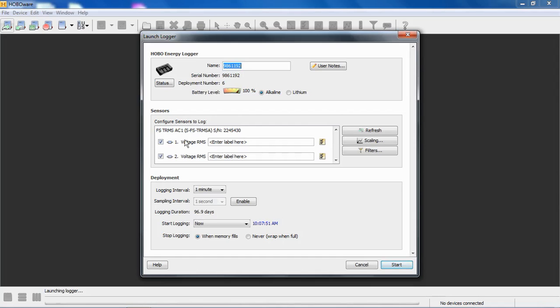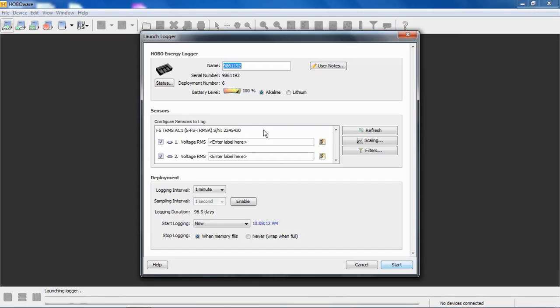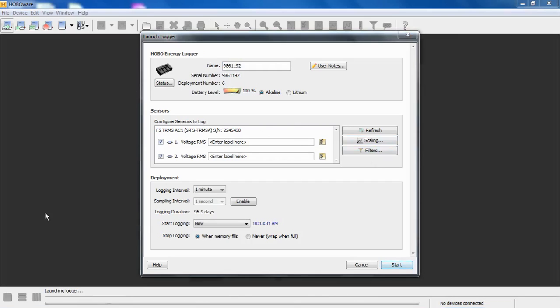Here we have this one module, two channels configured. The input to the TRMS module is looking for an AC, a very low voltage AC signal from either a current transformer or a potential transformer. So these need to be scaled in order to read out in your correct engineering units. This is the free version of HoboWare. The HoboWare Pro looks exactly the same, except you'll see a KWH assistant here, which would be grayed out because that only works with pulses. And this device is an analog-type device, AC input.